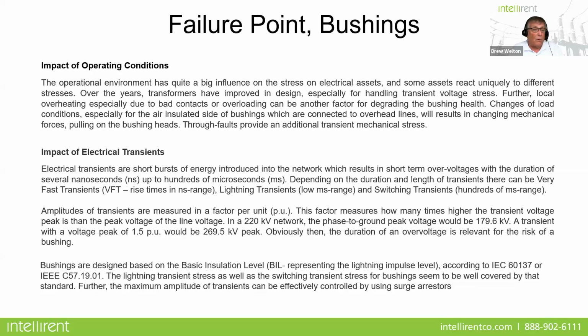Local overheating, especially due to bad contacts or overloading, can be another factor for degrading bushing health. Changes of load conditions, especially for the air insulated side of bushings, which are connected to overhead lines, result in changing mechanical forces pulling on bushing heads, through faults.